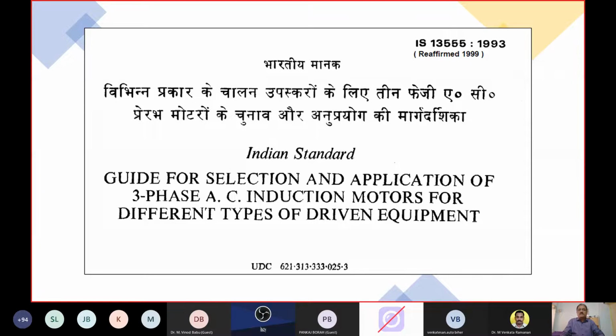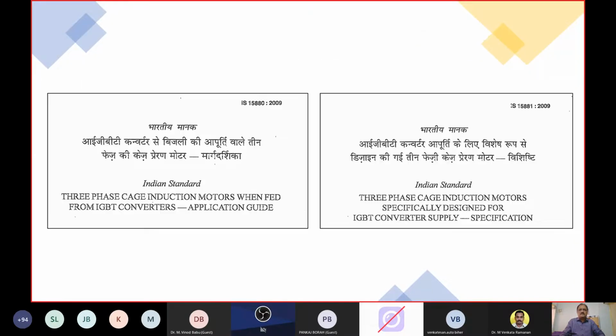Also it will help you to appreciate the fact that the industry at large does not pay a lot of respect or heed to what is recommended in this standard. If they did, then they would not freely replace motors from one location to another, one application to another application. Misapplication in industry is possibly the largest reason why motors fail. Approximately 60% of the failures, in my opinion, are because people freely replace motors from one application to another application. In that sense, IS 13555 requires a lot of understanding, thorough reading, and use in applications.